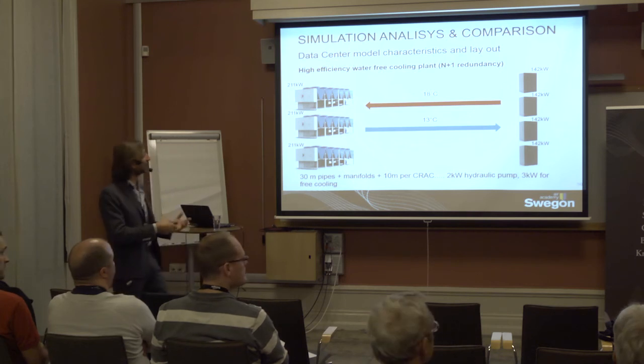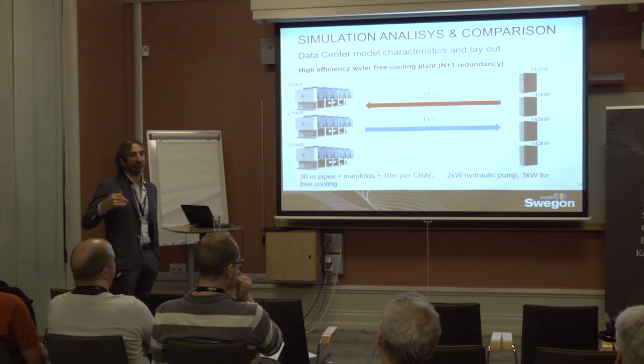Of course, we are making these free cooling chillers run together, so the logic is not the failure activation of a chiller. They are always active, to increase the efficiency of the system, because if every chiller runs in partial mode, it obviously has a higher efficiency. And the same is for the indoor units. The sum of these is higher than 400, but they can run in partial load mode. And we considered the pump to pump the water from 13 to 18 degrees inside and outside of the building, of course. And the comparison is made with a system like this one, using 4 different units, every one able to deliver 135 kW at the maximum cooling power. But they are running every one at 100 kW, so as to supply the 400 kW requested by the data center.